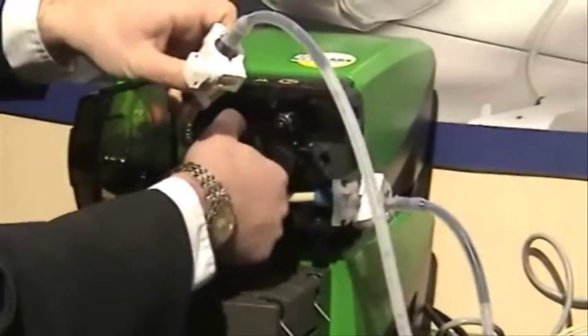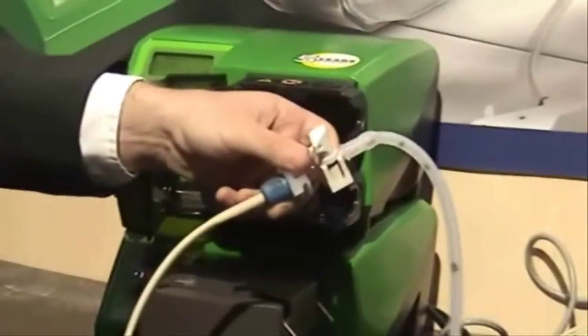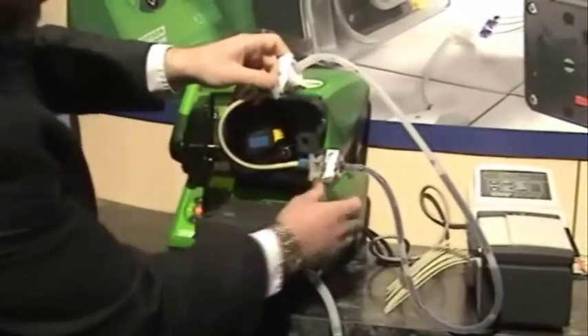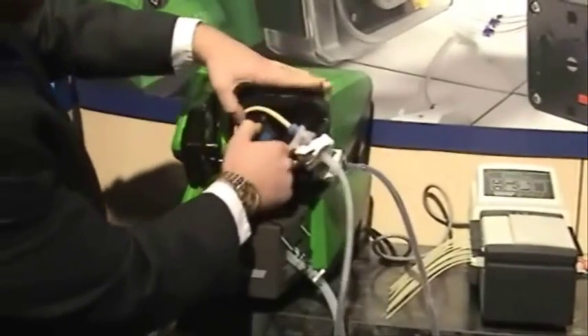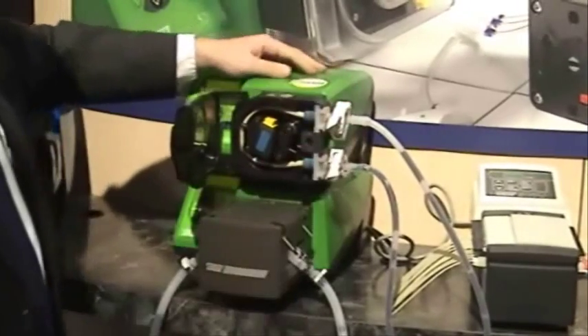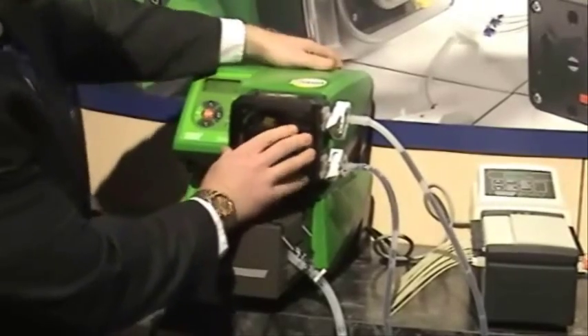To replace the tube, simply turn off the pump, open the door, and remove the tubing. Take a new tube element and insert it into the pump head. Of course, all Watson-Marlow tubing, like our LoadSure element shown here, is supplied with full QC documentation for ultimate traceability. There are no valves, seals, or other wetted parts to clean or replace. After positioning the tubing, close the door, and your pump is ready to begin operation again.